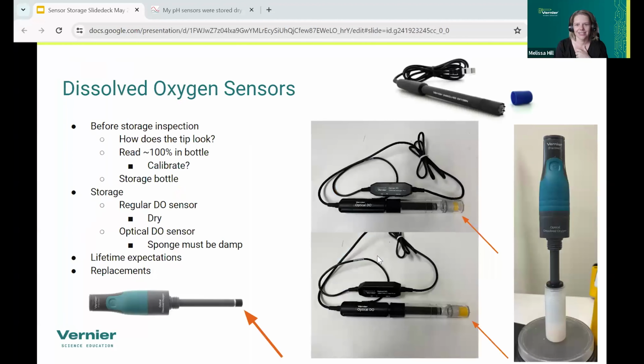All right. On to dissolved oxygen sensors. This is Colleen's area, so I'm going to pass it off to her. Fantastic. So dissolved oxygen sensors are pretty easy to store. The big thing is if you have some of the older electrode version that we have here, you want that to actually be stored completely dry. So you want to make sure there's no filling solution left within the tip.